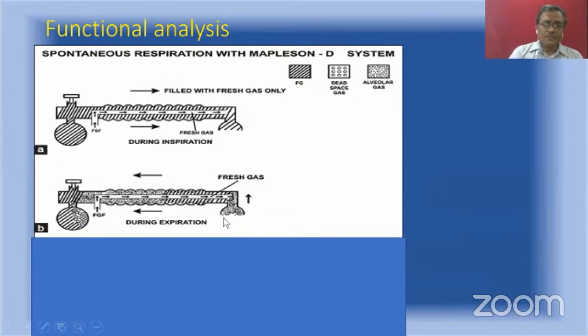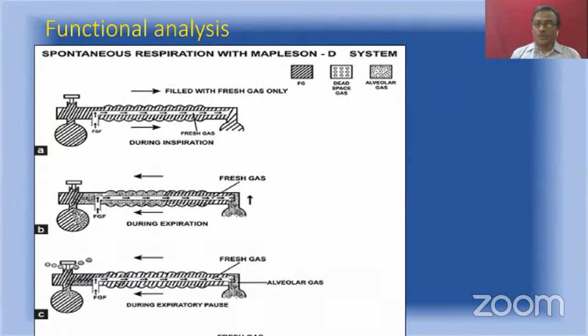So there is a mixing up of this alveolar gas and dead space gas with the fresh gas. And you can see these gases are reaching the reservoir bag, right? No confusion about that. Now we move on to the expiratory pause. See, in expiratory pause, there is no movement towards the reservoir bag from the patient side. Okay, but there is an inspiratory tube which carries fresh gas, which pushes the dead space and alveolar gas further towards the reservoir bag, which will increase the pressure in the system. Valve will be opening and the gas is going out. So fresh gas will be going out, alveolar gas will be going out, dead space gas also going out. Okay. Now we will see what is going to happen during next inspiration.